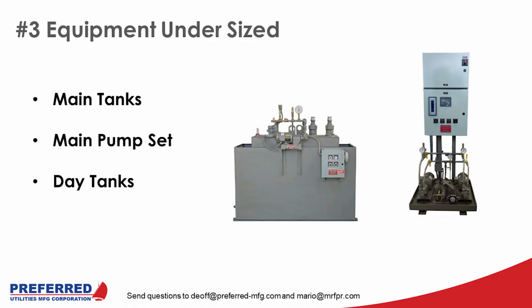Now that the genset is also requiring diesel for hours at a time, the system in certain cases is overloaded, perhaps undersized, with pressure fluctuations as fuel users come in and out. Another component that we found to be undersized in many cases was the main tank. Many facilities ran out of fuel. Many hospitals ran out of fuel.